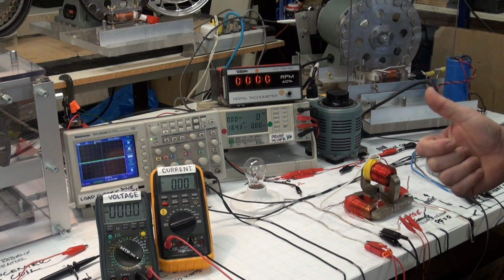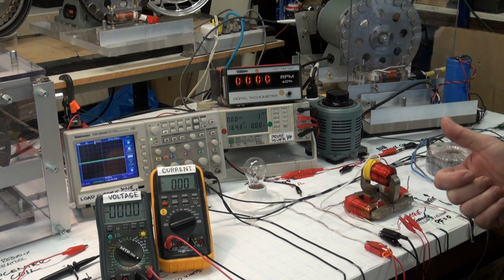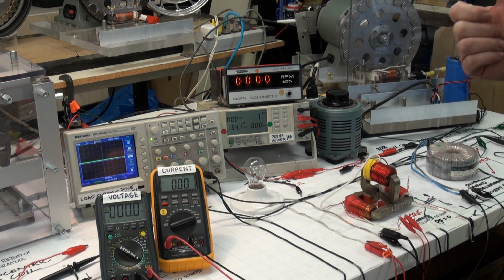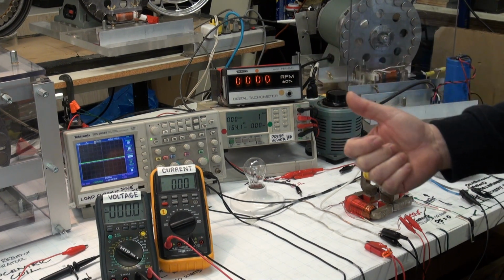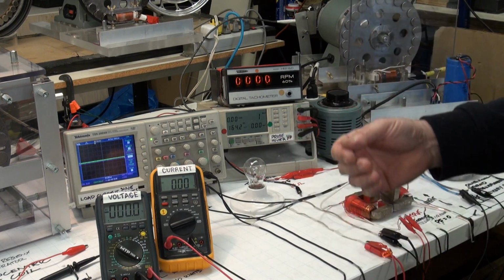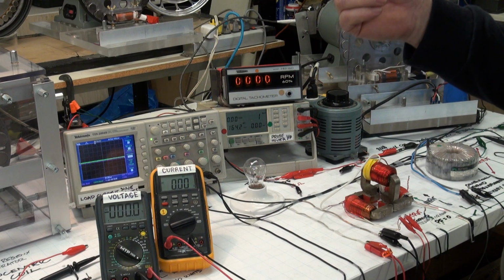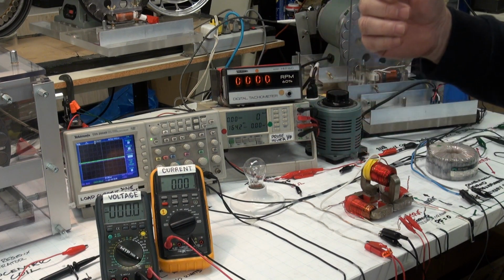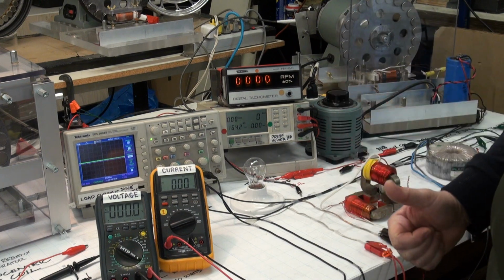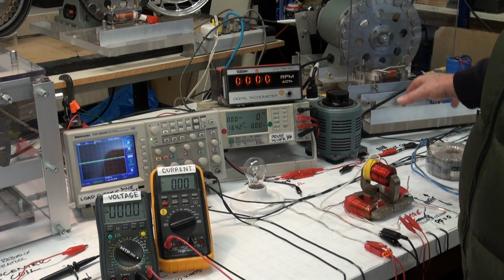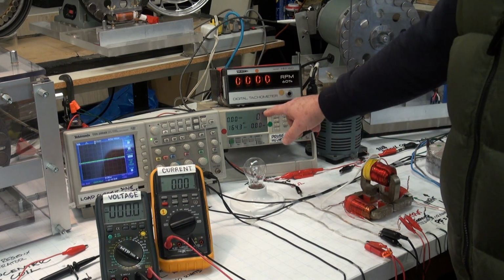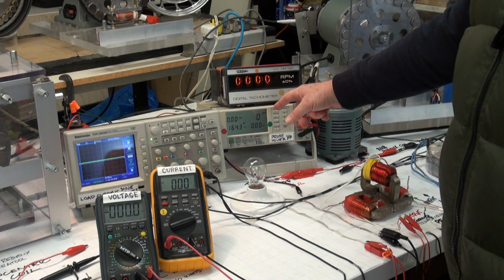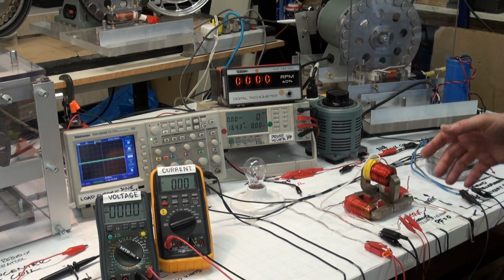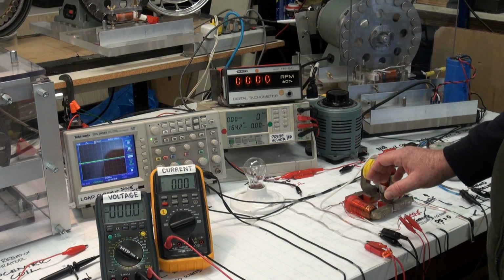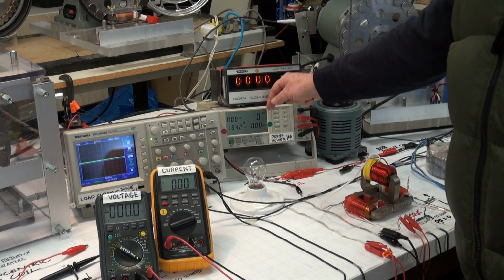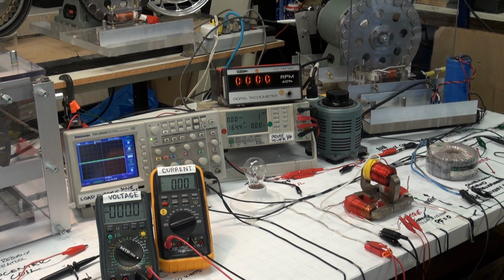Again, we're starting the system at a steady state speed. And that means that at steady state speed, the net torque in the drive shaft is zero. That means the power in the drive shaft, which is the torque times the speed, is zero because the torque is zero. So when we place the conventional transformer on load, this number will go up. In response, the speed will go down. And then when we place the bitoroid transformer on load, this number will go down and the speed will go up.